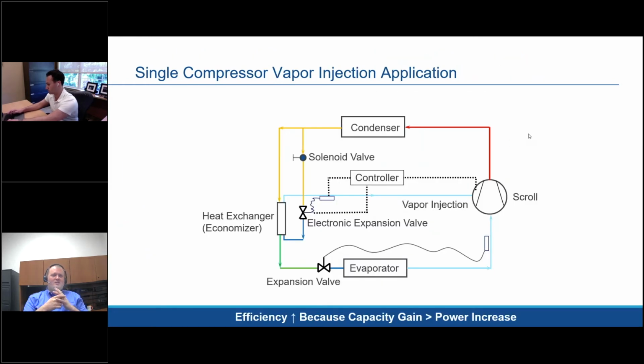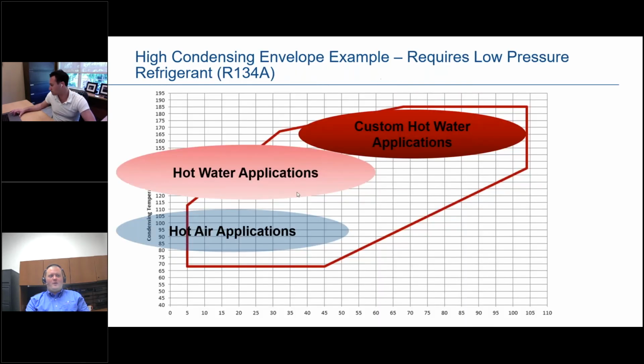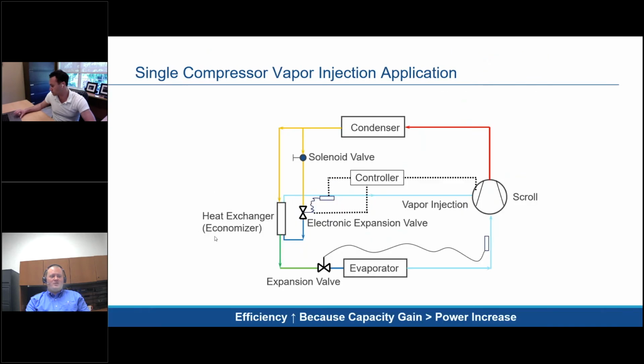And I'm going to jump here. This is going to answer some of that vapor injection questions, I believe. This is an example of a single compressor with vapor injection in the system. In today's systems, your typical system, you're going to have your compressor, your condenser, your evaporator, and your expansion valve. When you start adding in vapor or wet injection, you are going to add an extra heat exchanger, which is also known as an economizer. So you're going to come off that liquid line, and there's going to be a solenoid valve, typically, which you can open or shut in order to isolate the main system from the injection side of the system.